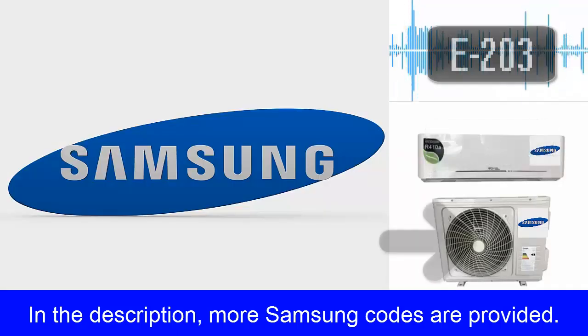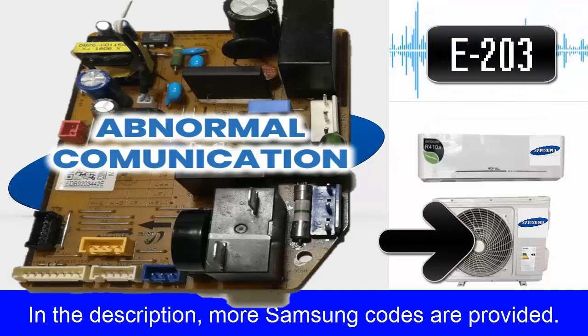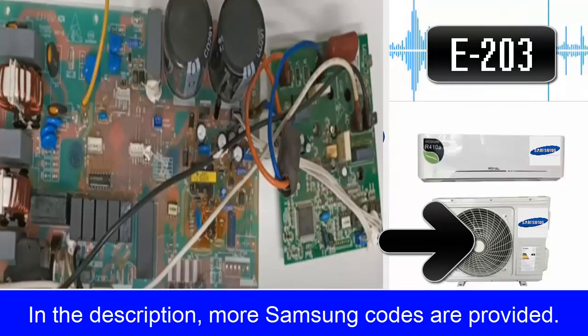7. Fault represented by error code E203. It indicates that the communication time between the main controller and the inverter controller has exceeded. Check the connections.